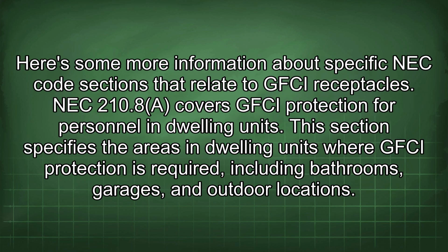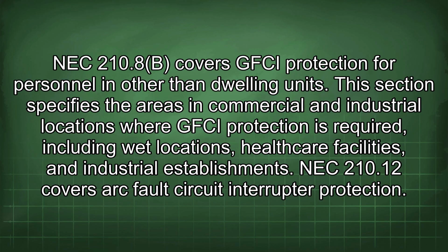Here's some more information about specific NEC code sections that relate to GFCI receptacles. NEC 210.8 covers GFCI protection for personnel in dwelling units. This section specifies the areas in dwelling units where GFCI protection is required, including bathrooms, garages, and outdoor locations. NEC 210.8(B) covers GFCI protection for personnel in other than dwelling units.